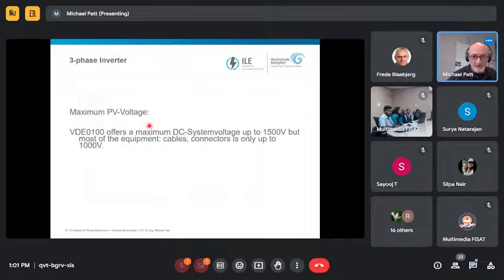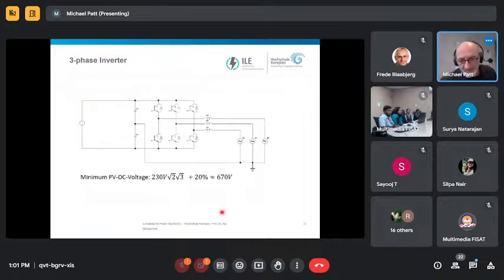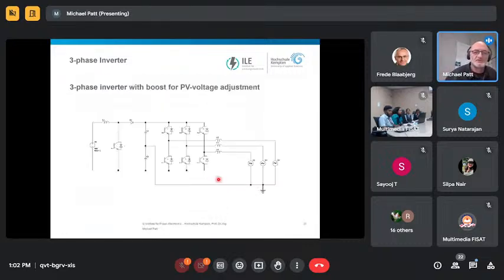So back to the slide with my 670 volt and my 60% temperature-based variation, it will not work over the year. Half of the time your three-phase PV inverter will be off. What to do? We take a boost inverter for PV voltage adjustment. This is a way to overcome this problem. We take a simple boost, but it will reduce the efficiency, so pay attention.